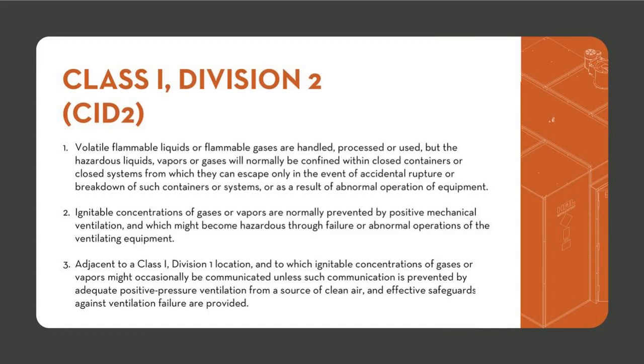And then on top of that, you have ethanol as a liquid at room temperature, so it's less combustible, with less surface area to volume ratio with that oxygen surrounding it. So it's not going to ignite the same way a vaporized gas will. So it's inherently less dangerous. That doesn't mean that you can't create a safe environment for these Class 1A solvents like butane. It just means that you have to follow stricter precautions, like C1D1.